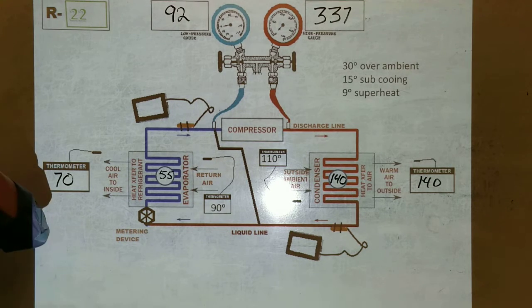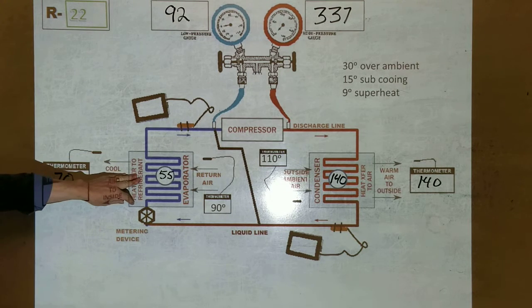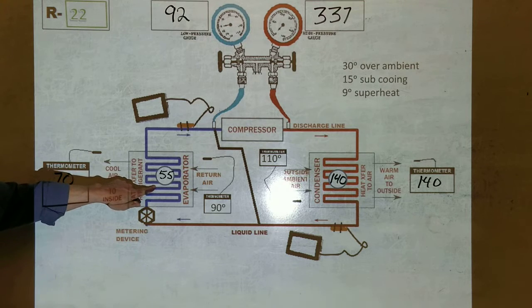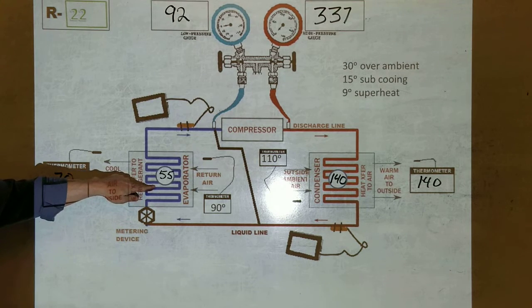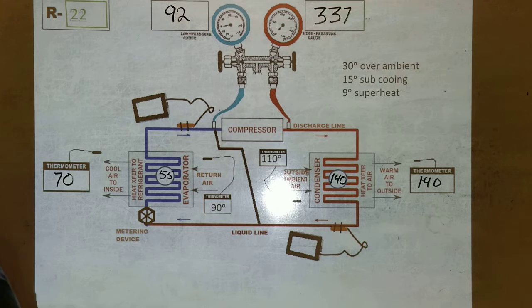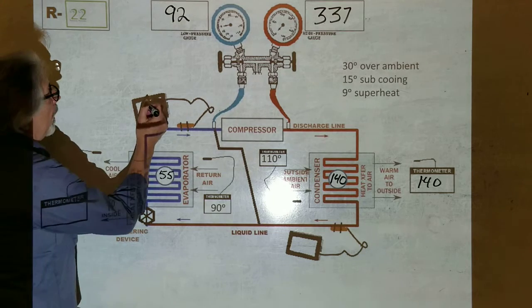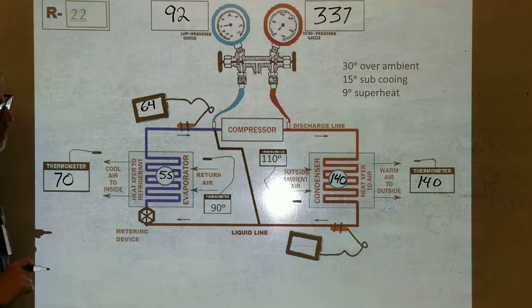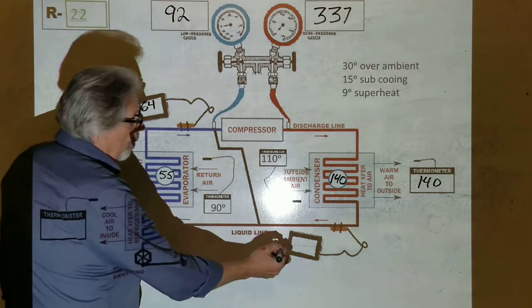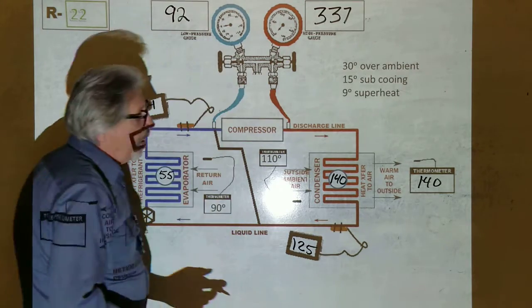Okay, so when we go to superheat and subcooling, this is what we're gonna do. We're gonna go from this temperature, right? Are we gonna go up or down for superheat? Okay, so what's 9 and 55? 64. So we're gonna read 64 degrees right here on this suction line. Isn't that amazing? Okay, what about our subcooling? Subcooling is now 15, so it'll be 125. 125 degrees on the liquid line.